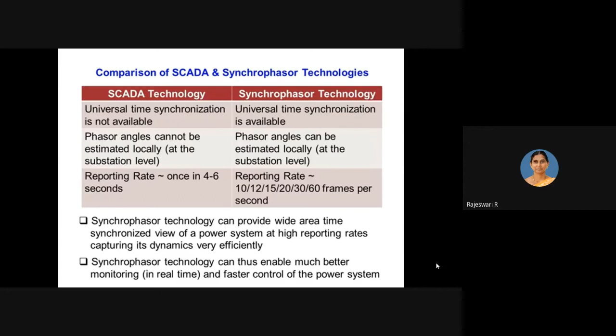And the reporting rate: the data rate is once in 4 to 6 seconds in case of SCADA technology, whereas synchrophasor technology gives even 60 frames, 60 data per second. So synchrophasor technology can provide a wide area time synchronized view of the power system at high reporting rate, capturing its dynamics very efficiently, so faster control action can be performed because of this perfect monitoring.